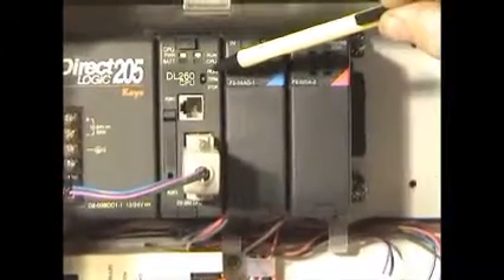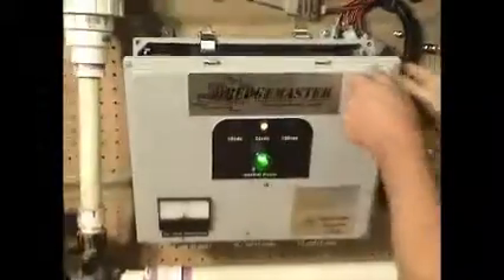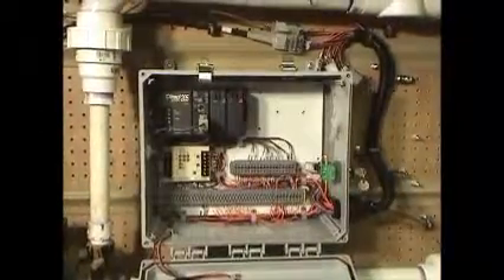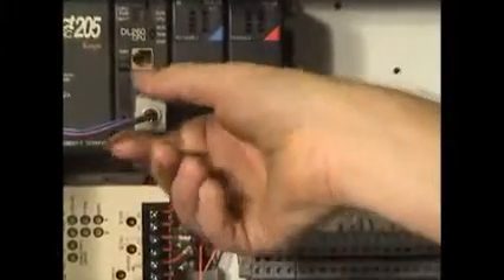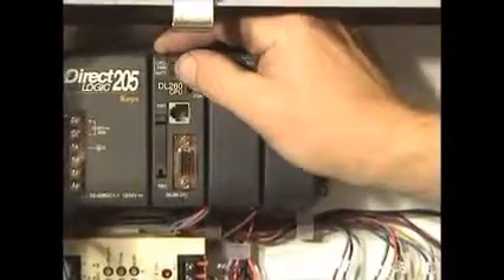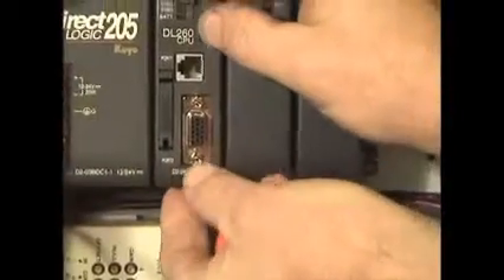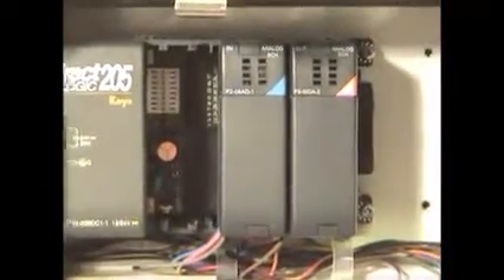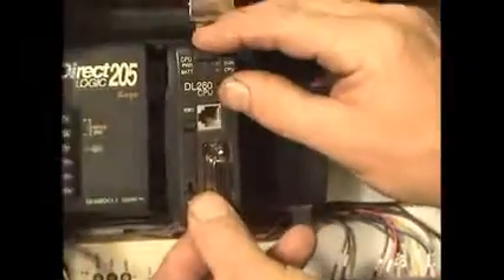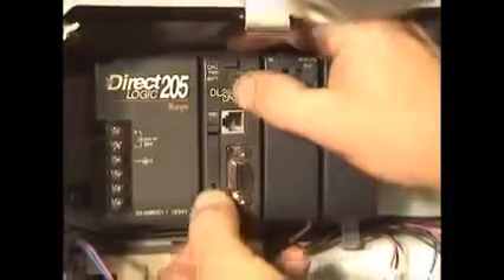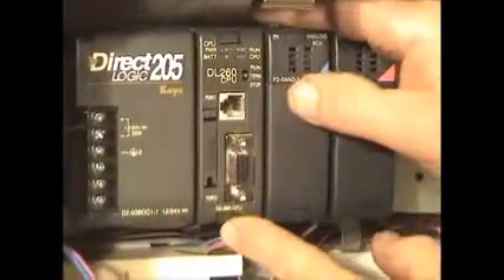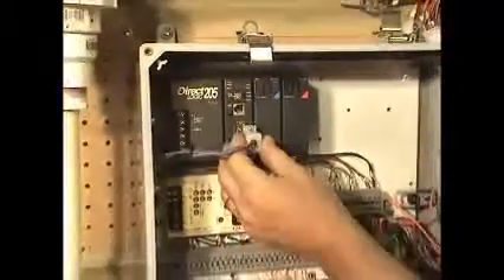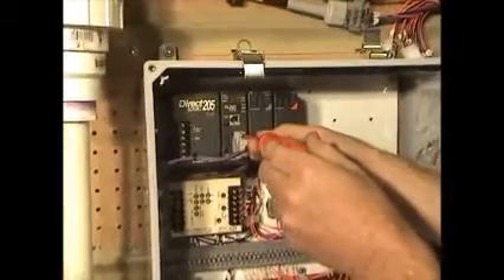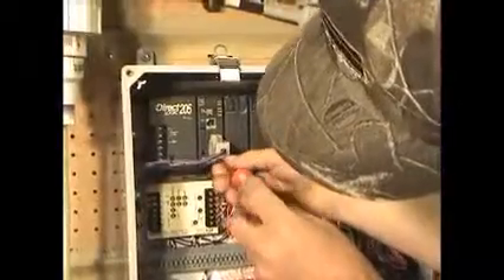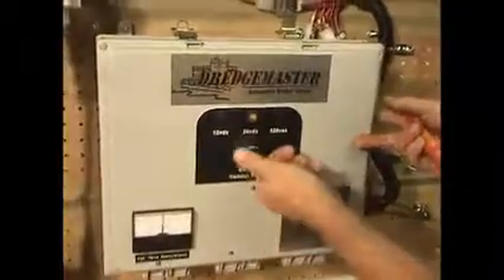In the event of a CPU failure, first thing to do is turn off the power. Next, you'll need to disconnect the communication cable by unscrewing the 2 top and bottom screws, pulling out the cable. Next, pull out the top and the bottom tabs, and then simply gently pull the module from the base plate. To replace a new CPU module, simply insert the module into the base plate, push it in until you hear a slight snap, push the two tabs in, hook up your communication cable, tighten the top and bottom screws, and turn the power back on.